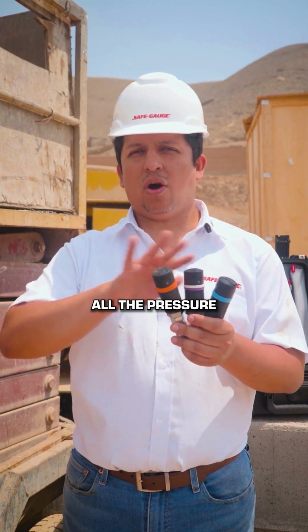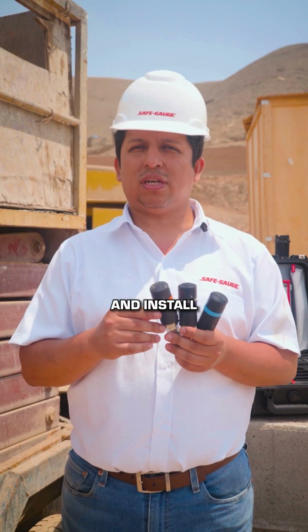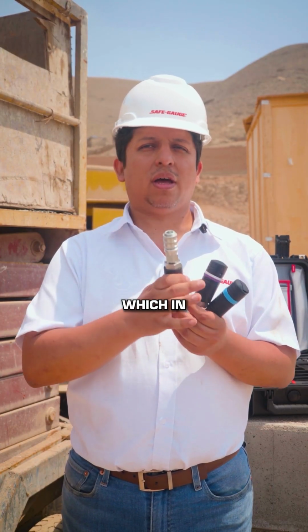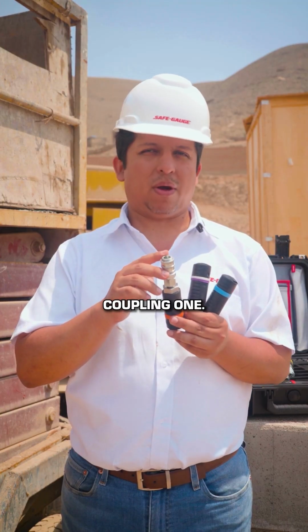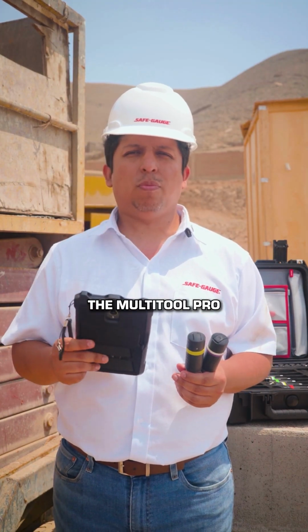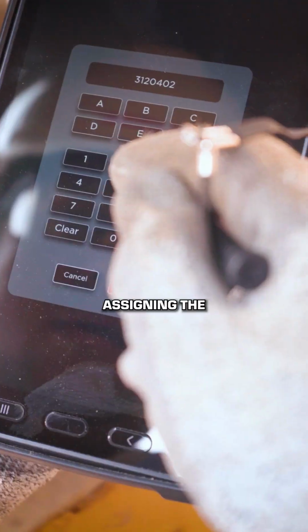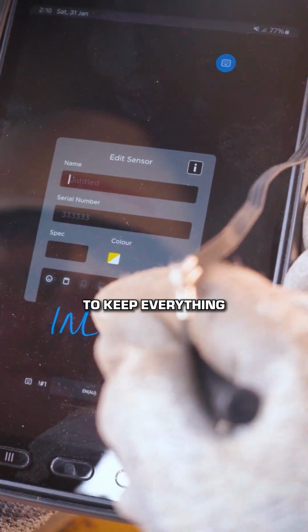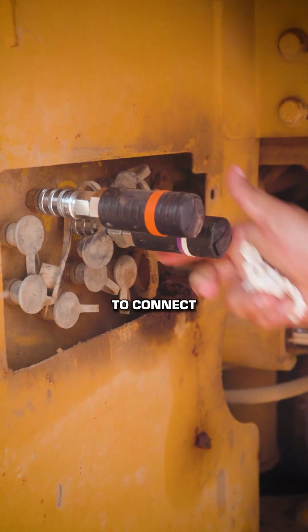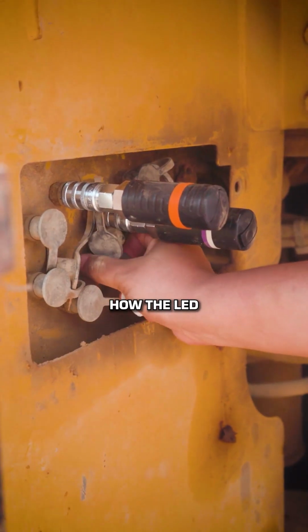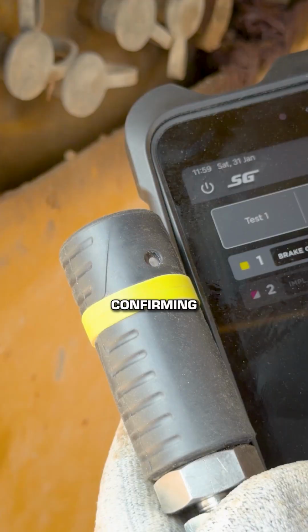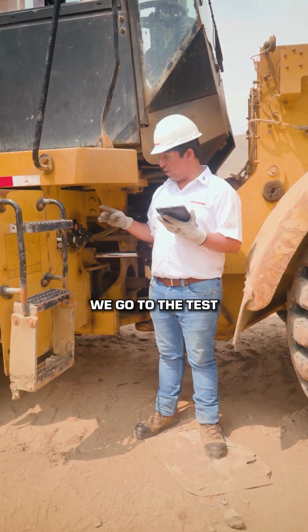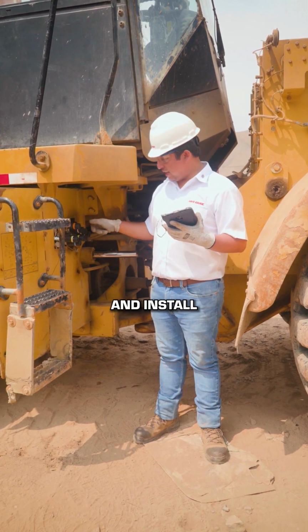First, we'll select all the pressure transducers to be used and install the appropriate connector, which in this case is a quick coupling one. Then we turn on the MultiTool Pro and configure each transducer, assigning the corresponding data to keep everything identified. Next, we proceed to connect each transducer and see how the LED changes from blue to green, confirming the connection is correct. We go to the test ports, clean each point, and install them.